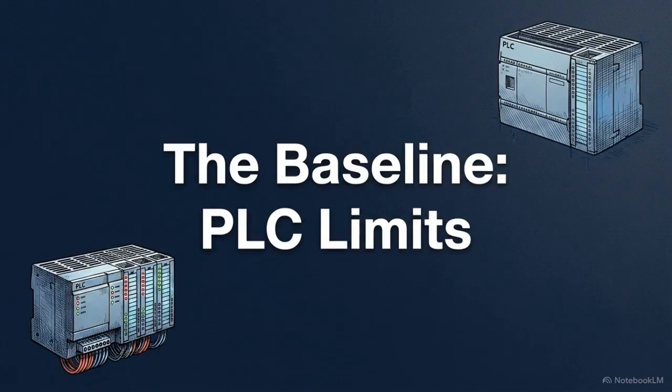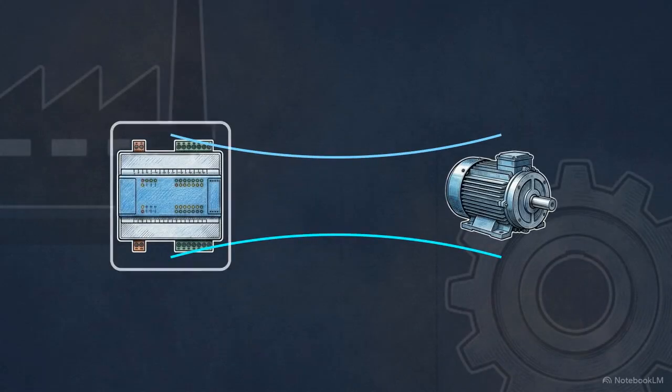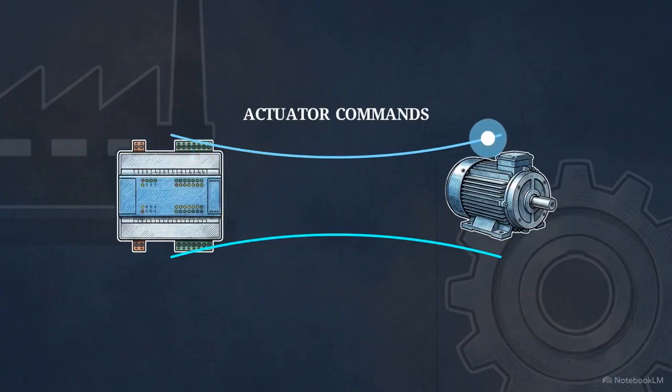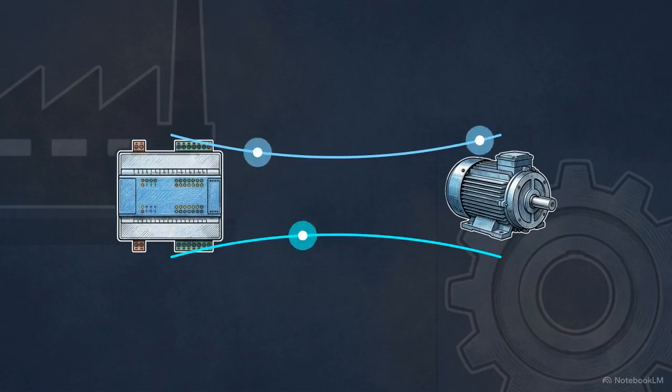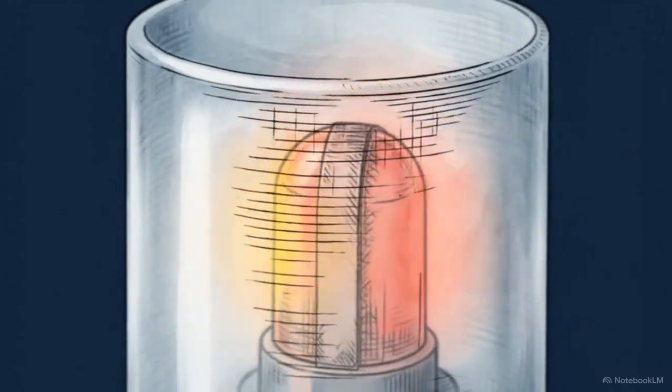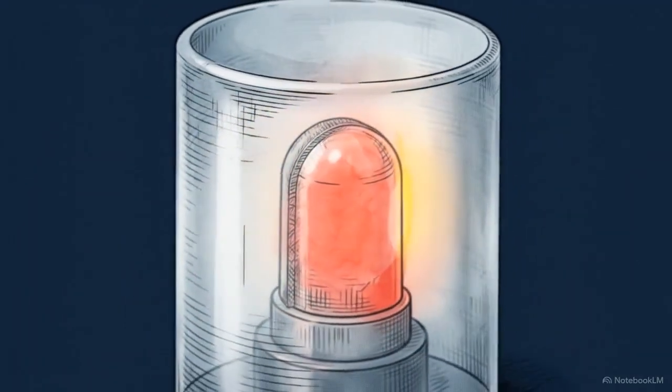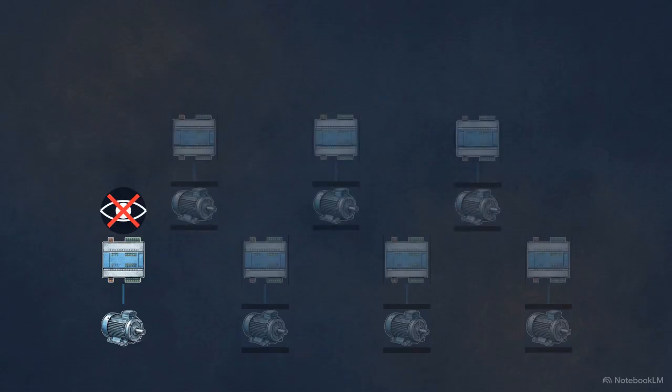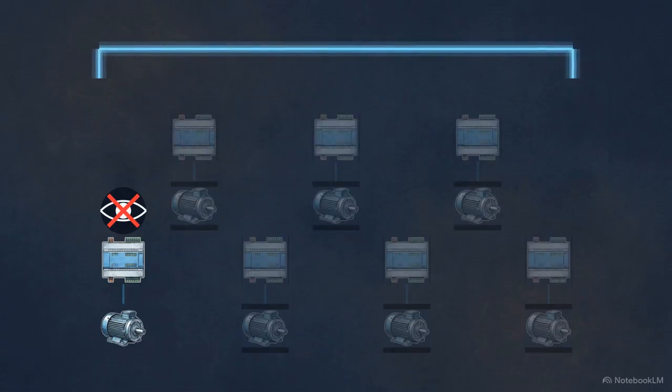This perspective aligns individual machine logic with the logistical requirements of a complete industrial facility. To understand the macro system, we must first establish the exact operational limits of a single programmable logic controller. This schematic shows how a PLC is designed specifically to control a single machine or an isolated, self-contained process. Within this closed loop, the PLC handles physical execution, reading localized sensors and firing physical actuators. This localized control operates at fast millisecond scan times to ensure reliability, but it functions entirely within a silo. The PLC is a dedicated, localized brain, yet it is blind to the operations of the rest of the factory. Coordinating multiple machines requires a higher-level system.